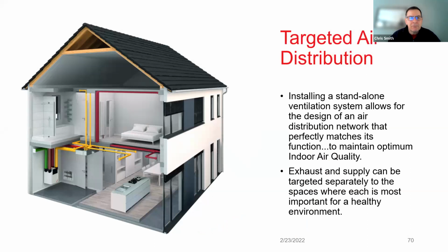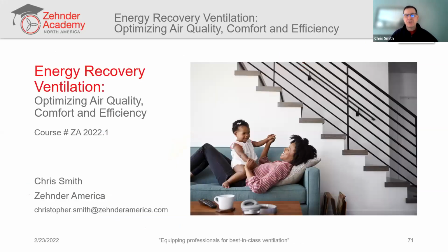By contrast, a system designed and installed specifically for indoor air quality results is going to be a targeted air distribution system that will extract air from the bathrooms and the kitchens. It will remove that stale air from those polluted areas, recover the energy from that stale air, deliver the energy to cold incoming fresh air, and then deliver that fresh air primarily to bedrooms and other living spaces, optimizing the indoor air quality in the living spaces where it matters most. So these are some of the features that you want to look for.